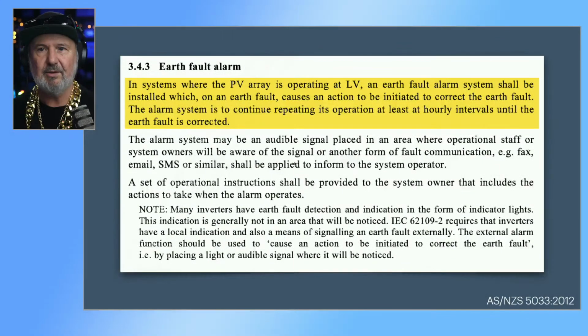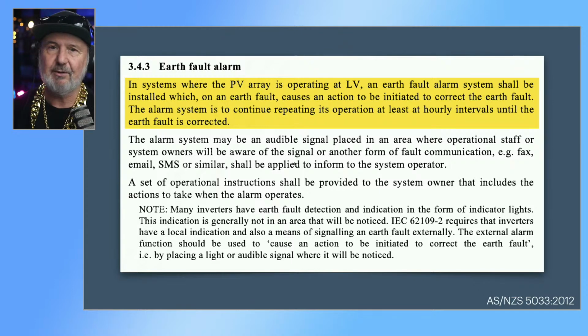Yeah, so where are we at? Okay, so let's just dive into some of the clauses now. And what I've done, I've gone back in time to the 2012 edition, particularly for the Kiwis that are still operating under the standard. And it starts with earth fault alarm requirements. They've been around since the 2012 edition, currently the referenced cited version in New Zealand, long since superseded in Australia.